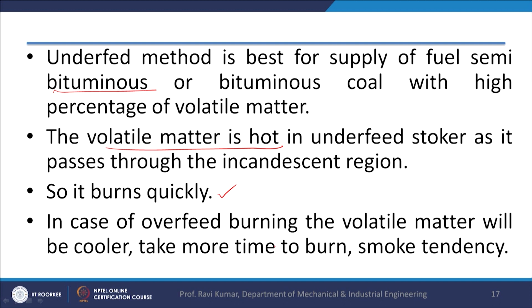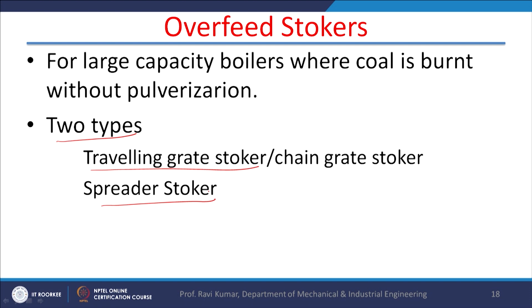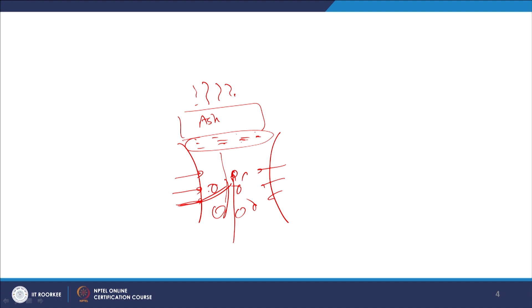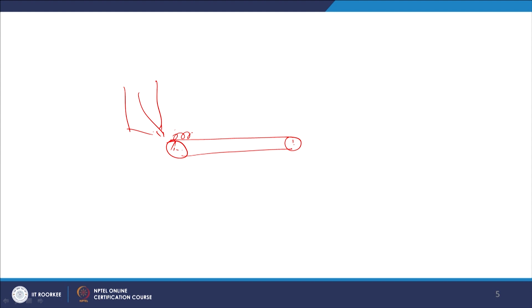Now, for feeding the coal onto the grate or the burning place, there are two types of methods. One is the travelling grate stoker, another is the spreader stoker. Now, in the travelling grate stoker, there are two sprockets, and on the sprockets there is a chain fixed to them, and on this bed the coal is fed. Suppose coal is fed from this side to this bed, and this coal moves on this bed.